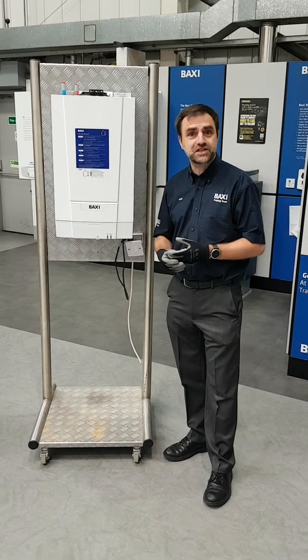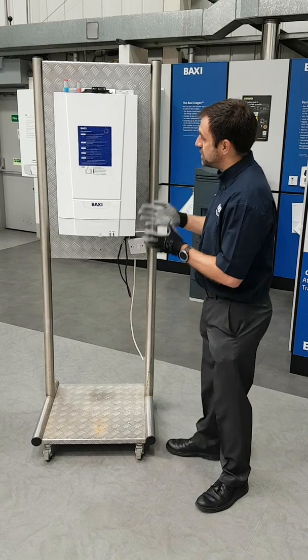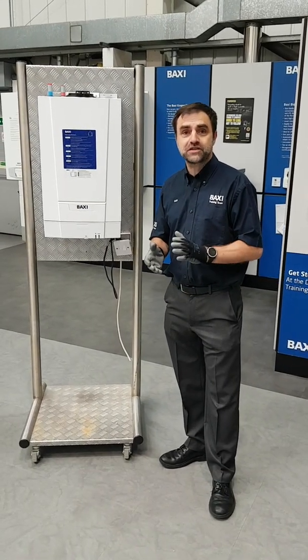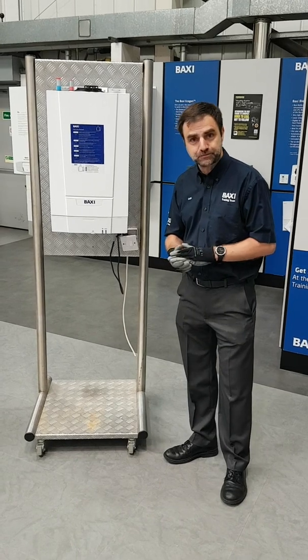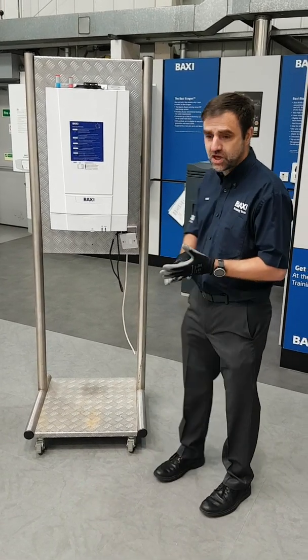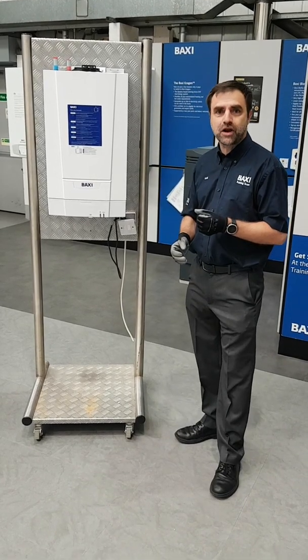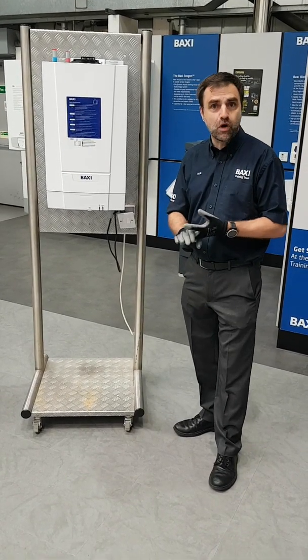We're building on the success of the 600 heat, and what we have here is a compact boiler. It is 370 wide, it is 270 deep, so it's perfect for a cupboard fit. It's got a range of options which include a top and rear flue. It also doesn't require a pump overrun, so it's just switch live neutral earth wiring in.